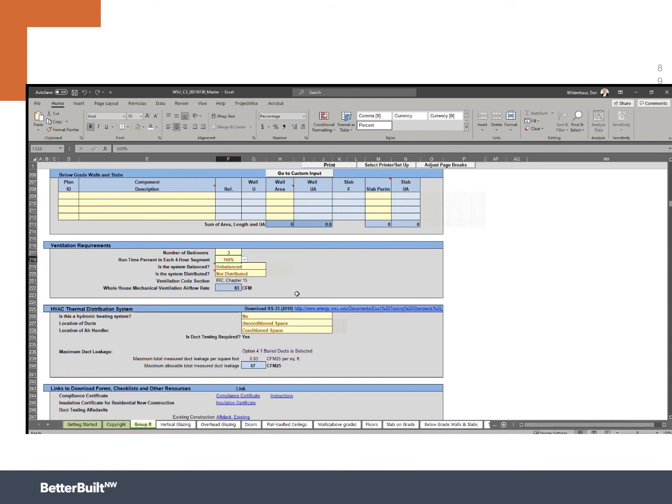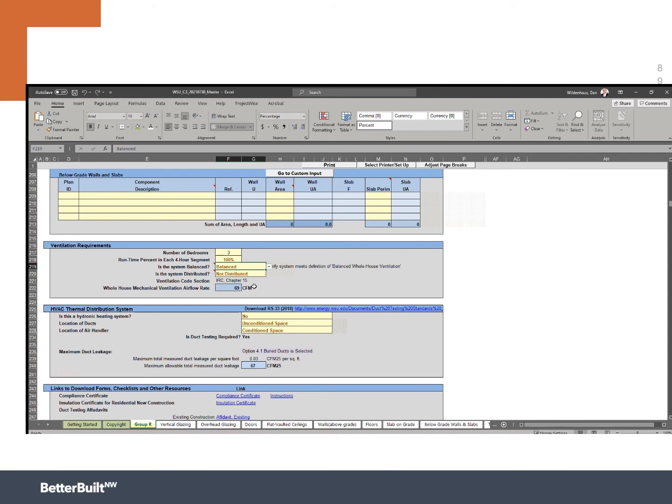Now, one of the big benefits should you make the decision to go to balanced ventilation is you're going to reduce the total need of airflow. So I'm going to switch this to balanced. And now I went from 83 down to 69 CFM. I could make it even a lower ventilation rate if I also made sure that I was distributing the air everywhere.